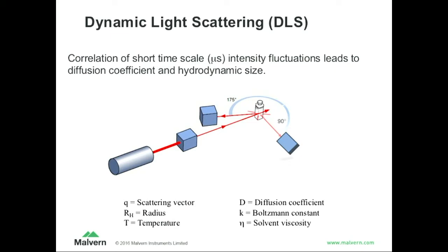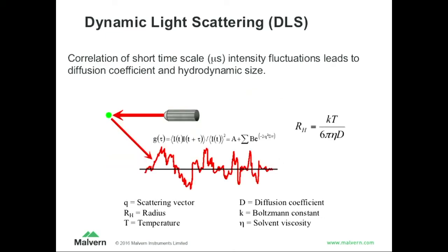We shine a light into a sample and look at maybe 175 or 90 degrees — it doesn't really matter. The core is we're looking at the sample and then we look at these intensity fluctuations. The red line that you see there shows the intensity fluctuations, and we statistically analyze them by looking at the intensity and comparing it with itself. We take a photo of the sample, and a short time later we take another photo, and if the other one is right on top of it, there's a strong correlation. If you take the second photo much later, you don't get a good overlap anymore — it slowly grays out — and that gives you a characteristic timescale of how fast things move away from their position.